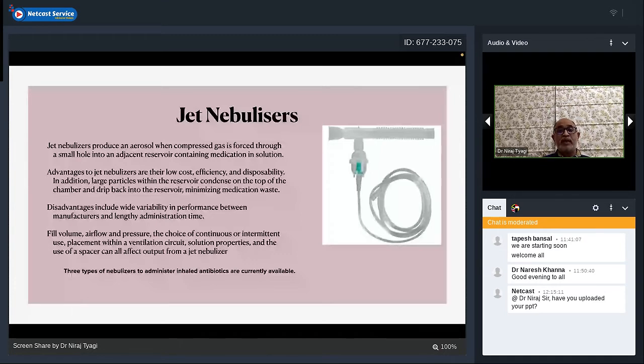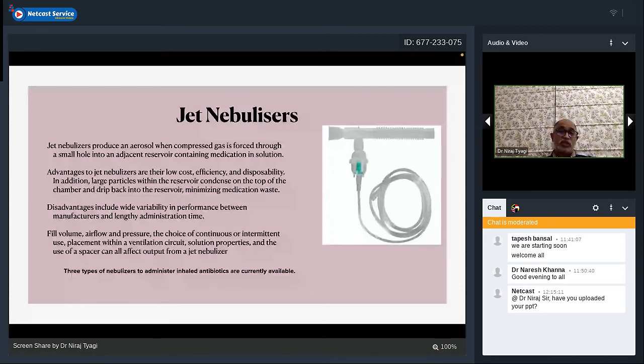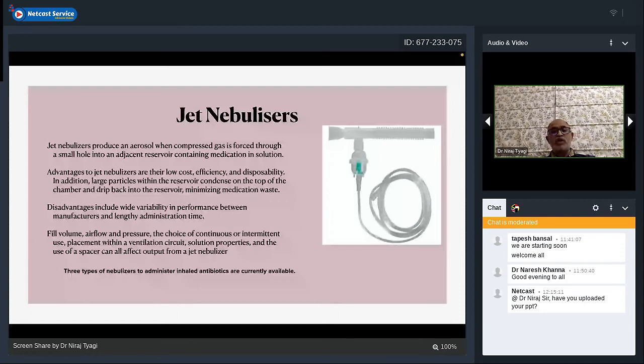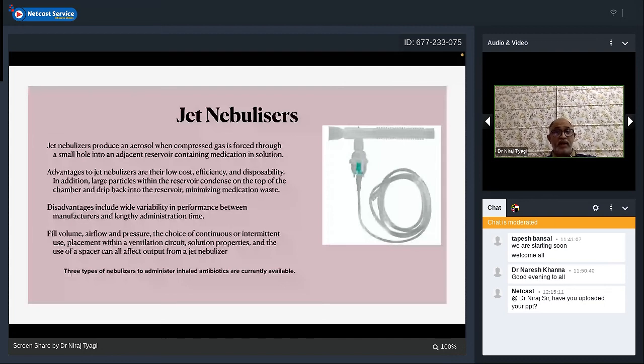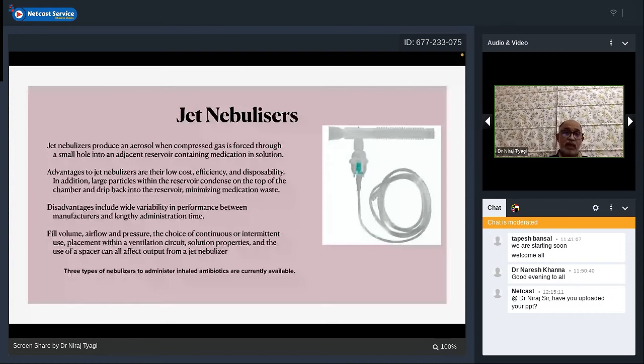Jet nebulizers use a compressed gas venturi mechanism — simple, low cost, well-tested, disposable. Large particles condense on top of the chamber and drip back into the reservoir, minimizing medication waste. The disadvantage is that this device typically needs 15–20 minutes of nebulization to deliver 4–5 mL of reconstituted medication. Fill volume, air flow and pressure, and the choice of continuous versus intermittent use are key variables. Solution properties and use of a spacer also affect output.